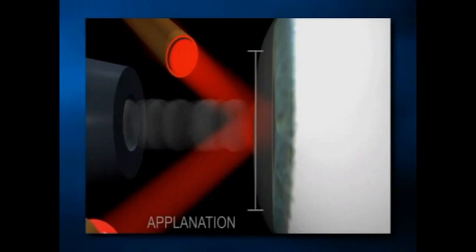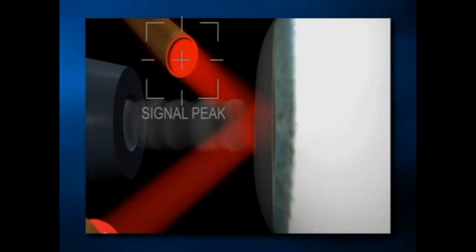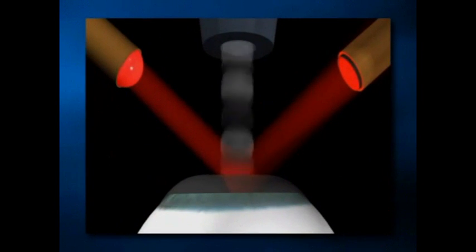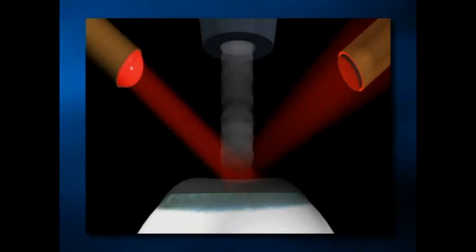When applanation is achieved, the reflected light is nearly collimated and the detector registers a signal peak, causing the pressure transducer to record the applanation pressure. Following applanation, the air pulse continues to impinge upon the cornea, causing it to deflect into a state of slight concavity. The reflected infrared light once again becomes dispersed and the detector signal amplitude decreases.